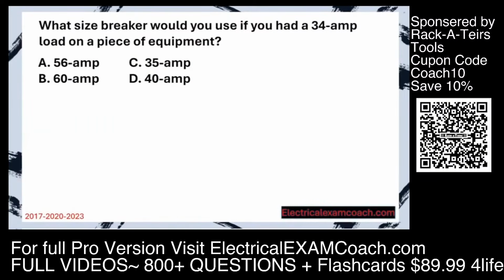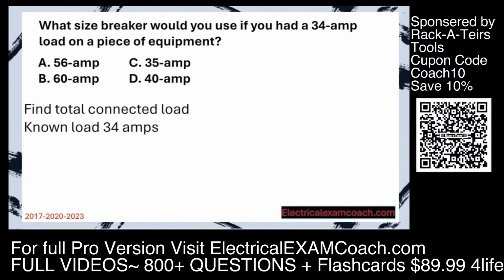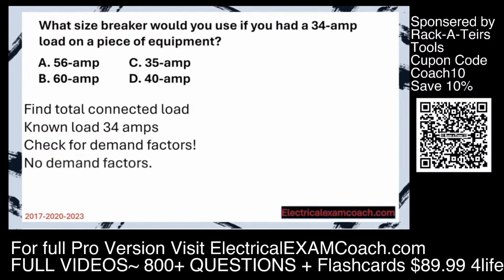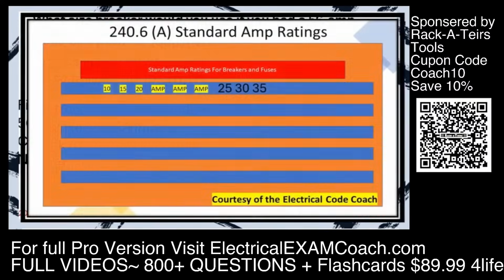Great job. What size breaker would you use if you had a 34 amp load on a piece of equipment? Step 1, find the total connected load. The known load as of right now is 34 amps, but we gotta check for demand factors. There are no continuous loads, and there are also no specific pieces of equipment, so therefore there are no demand factors. We're gonna head to our table 240.6(A), and we're gonna choose the next size up, which in this case would be a 35 amp breaker.